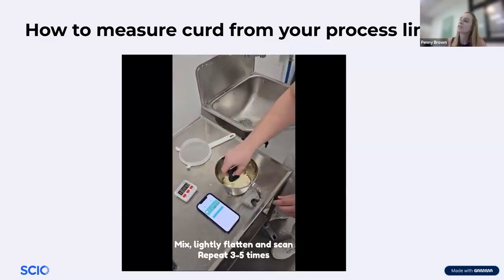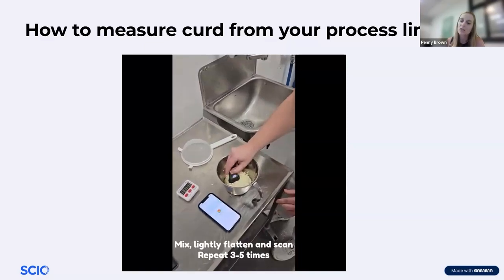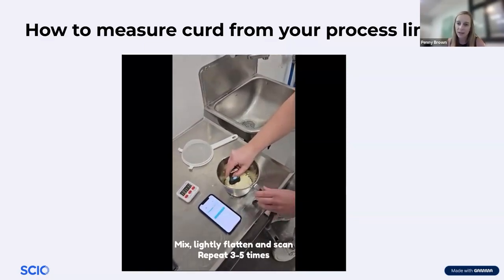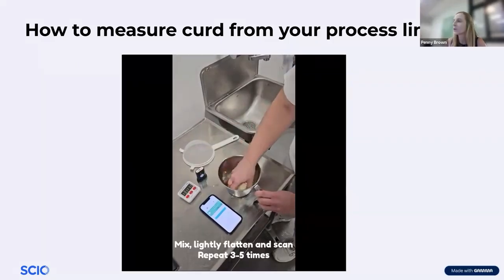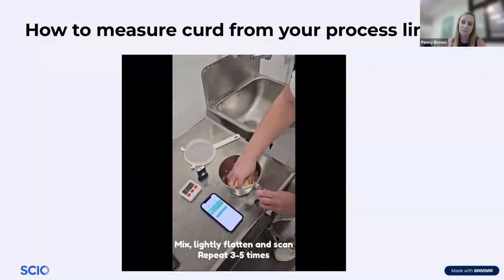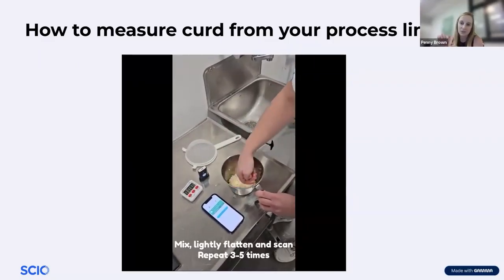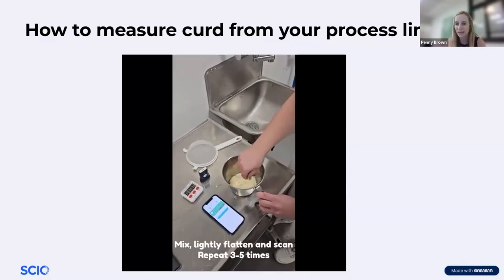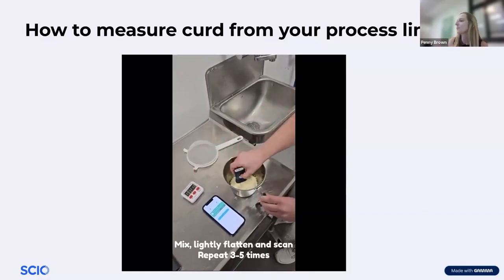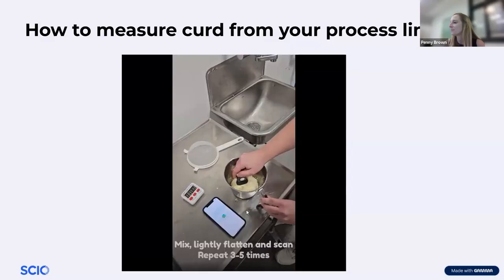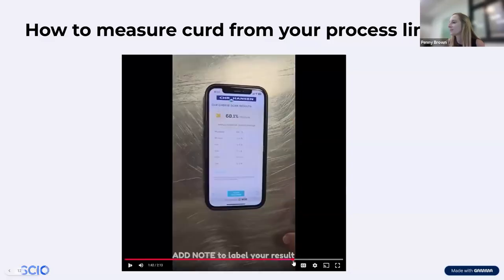The other thing that you'll notice he's doing is pressing the sample down to create a flat surface. The way that the product works is that the flatter the surface you have, the more accurate your result will be. So we really want to avoid having large mountains or little humps in your sample. You really want to have that flat. All right, I'll just skip forward a little bit.